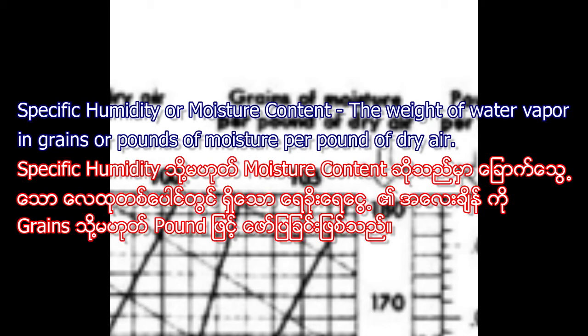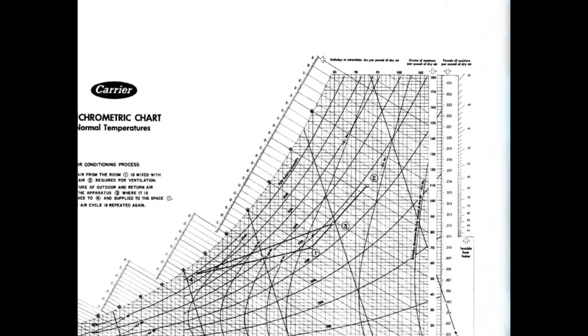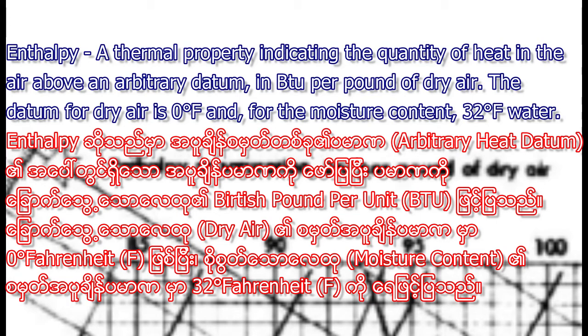Enthalpy is a thermal property indicating the quantity of heat in the air above an arbitrary datum, expressed in BTU per pound of dry air. The datum for dry air is 0 degrees Fahrenheit and for the moisture content, 32 degrees Fahrenheit water.